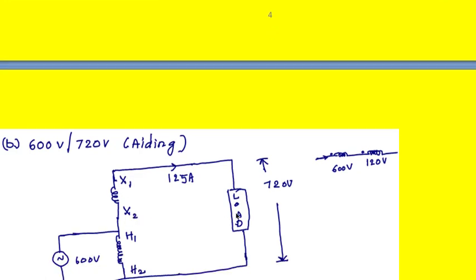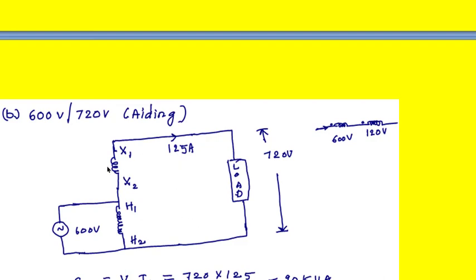The connection is X2 here, making it series aiding. The LV winding current capacity is 125 amperes, and since the LV winding is connected in series with the load, that current flows through the load. The load terminal voltage is 720 volts, so the kVA rating SB = V2 × I2 = 720 × 125 ÷ 1000 = 90 kVA.